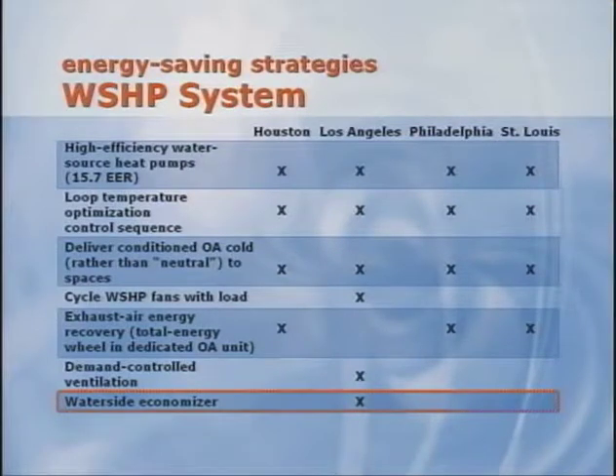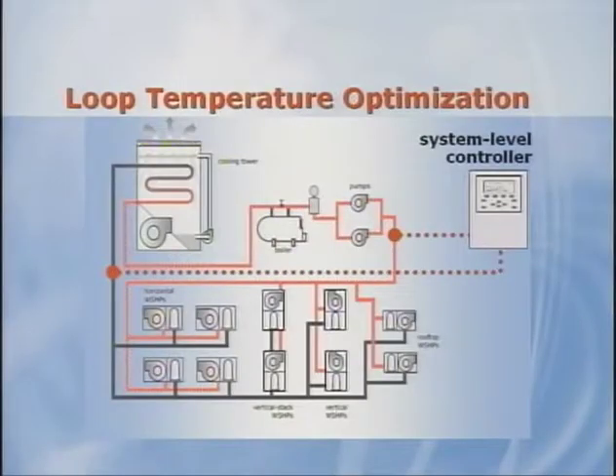The configuration is similar to the self-contained units, as the waterside economizer coil is mounted at the inlet of the heat pump. When the temperature of the water loop is cool enough, this coil can be used to pre-cool the air and save compressor energy. Let's review the loop temperature optimization strategy since it's unique to water source heat pump systems. A system-level controller is used to operate the pumps and coordinate cooling tower and boiler operation. To maximize the energy-related benefits of this system, the loop water temperature is allowed to float over a wide range, for example, between 60 and 90 degrees.